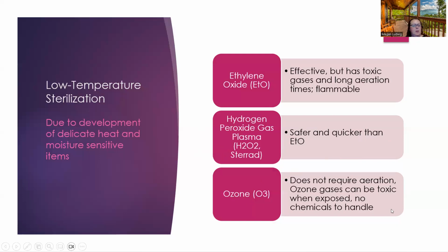Ozone I wouldn't say it's as common. I don't think any facility I've worked at has had the ozone sterilizer. But it is unique in that it does not require an aeration time, but the ozone gases can be toxic.